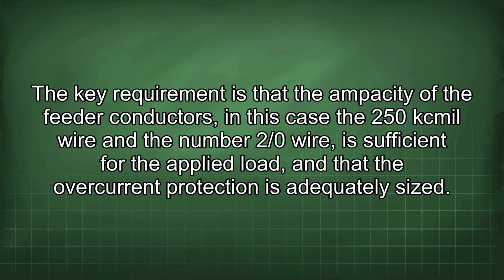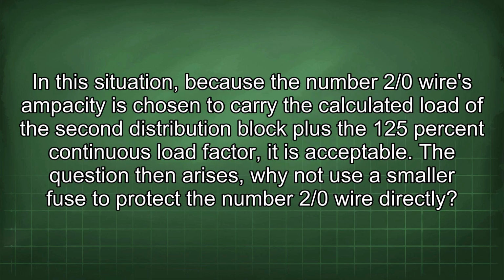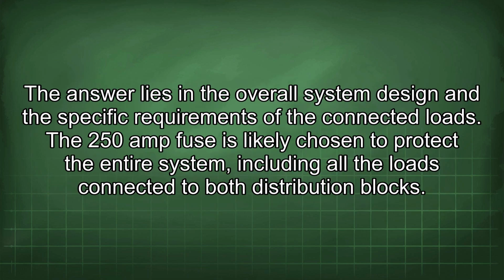The key requirement is that the ampacity of the feeder conductors, in this case the 250 kcmil wire and the number 2/0 wire, is sufficient for the applied load and that the overcurrent protection is adequately sized. In this situation, because the number 2/0 wire's ampacity is chosen to carry the calculated load of the second distribution block plus the 125% continuous load factor, it is acceptable. The question then arises, why not use a smaller fuse to protect the number 2/0 wire directly? The answer lies in the overall system design and the specific requirements of the connected loads.